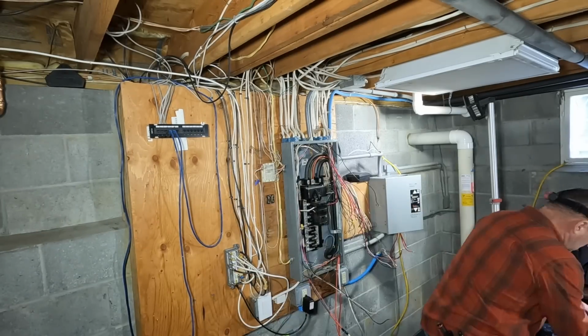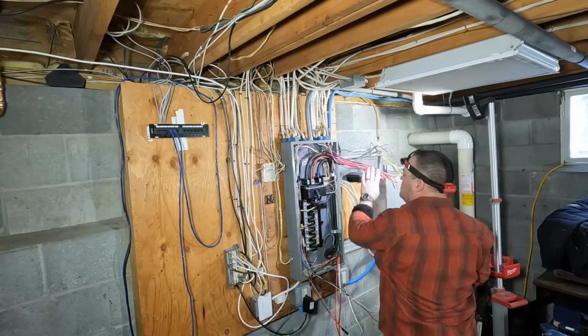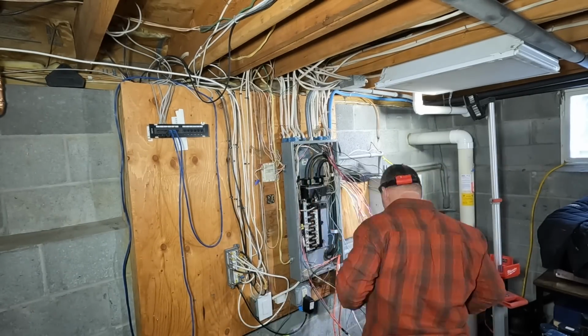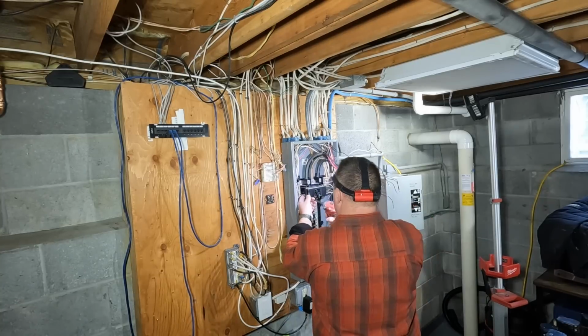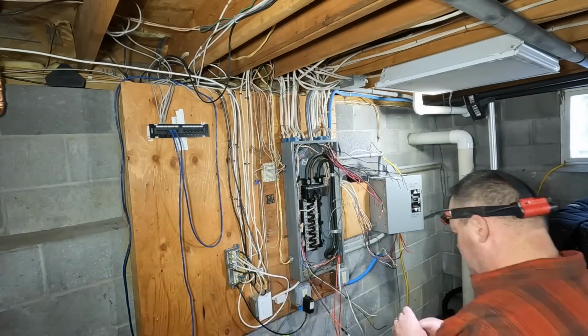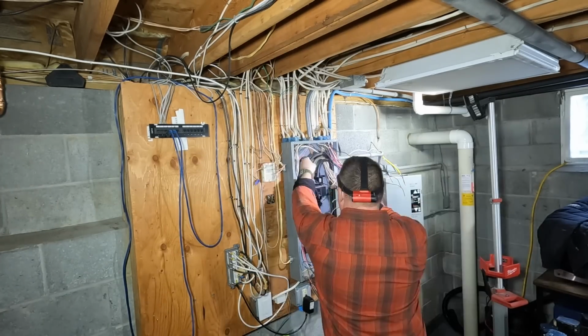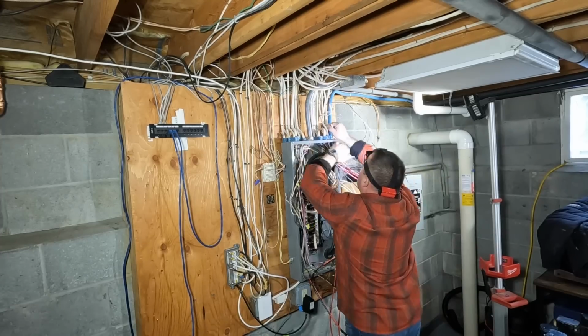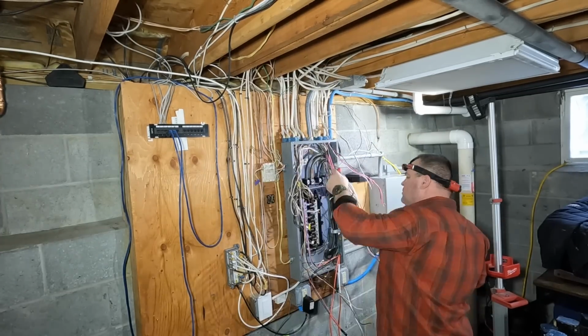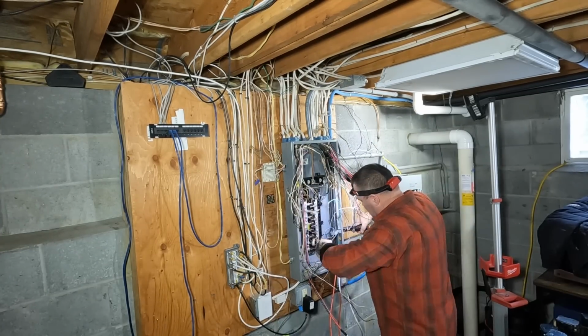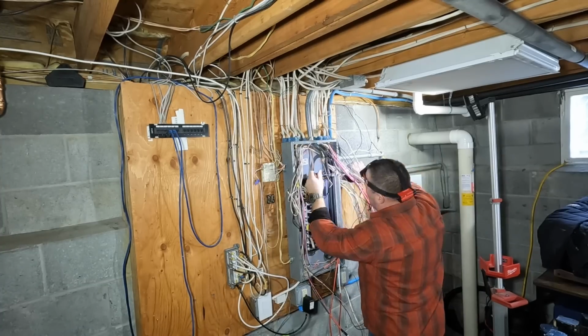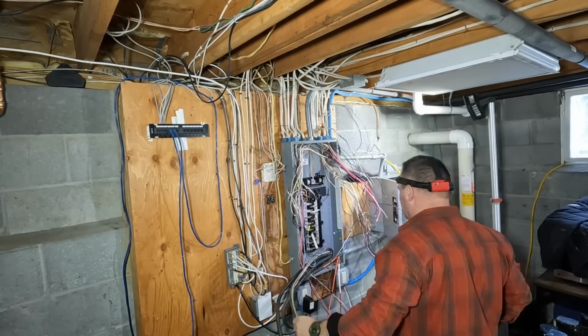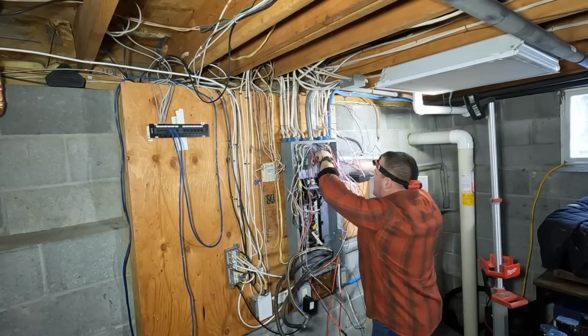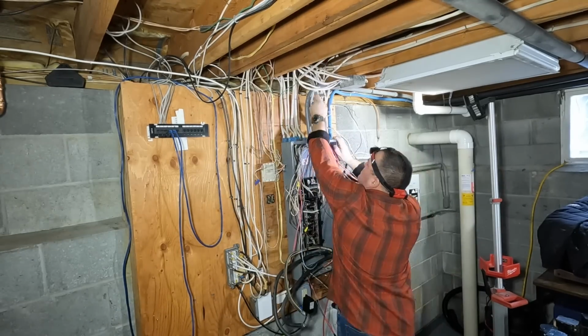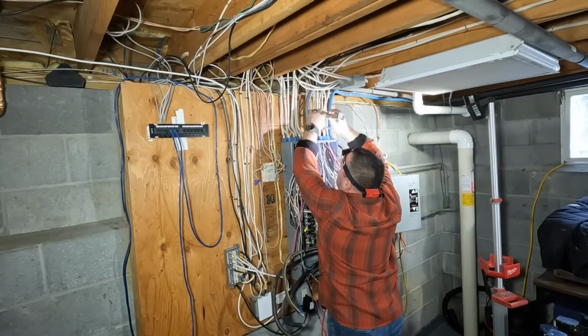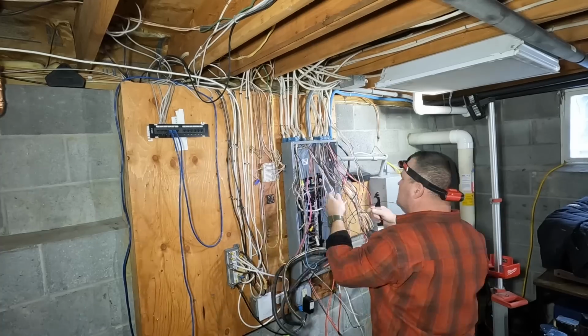The voltage testers that I'm using are made by Fluke. They're called Field Sense, and what that does is it provides an artificial grounding conductor for voltage connections without actually removing any of the terminations, such as wire nuts, to verify for voltage. You can actually read right through the conductors whether or not that conductor has voltage or not, which is really nice. Sometimes I forget I even have them, but I really do like using that Field Sense feature. So from here on out, we're just going to be removing all of these branch circuits.